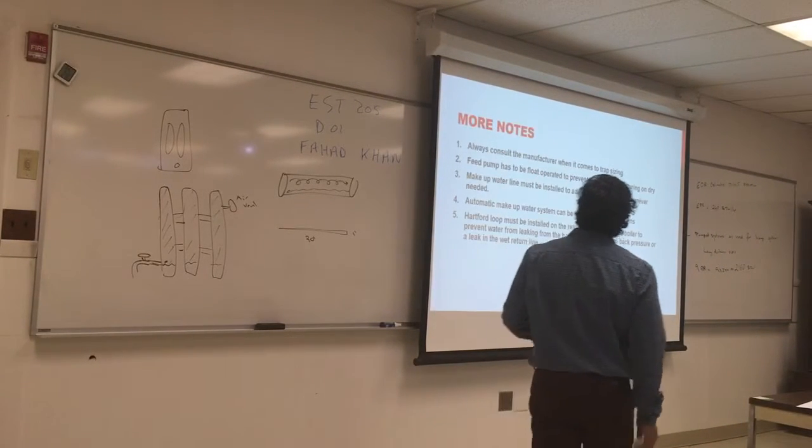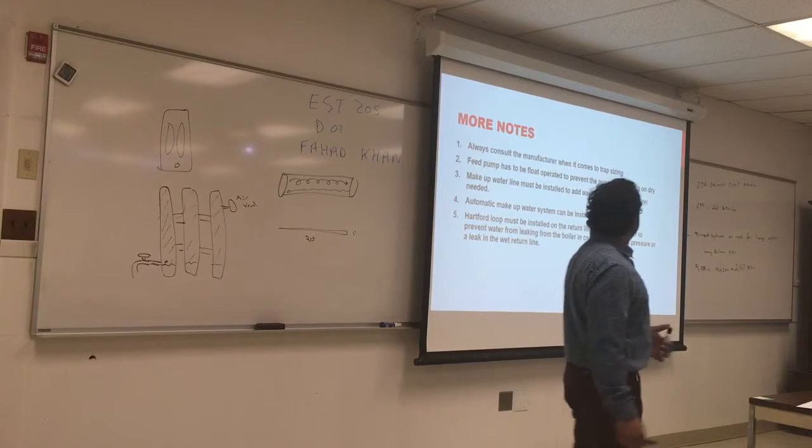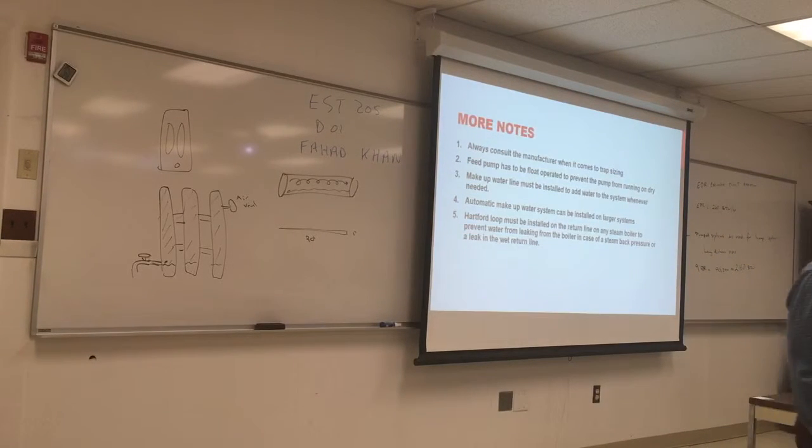Okay. So always consult with the manufacturer when it comes to trap sizing. Trap sizing is not one size fits all, and they have some numbers to be gauged to. So the rate of steam and air coming out should be manageable, because again, you don't want to shock the system. What does that mean? Let's say the radiator is very cold at 40 or 50, or the system is starting from scratch, like from zero. You might blow the system.